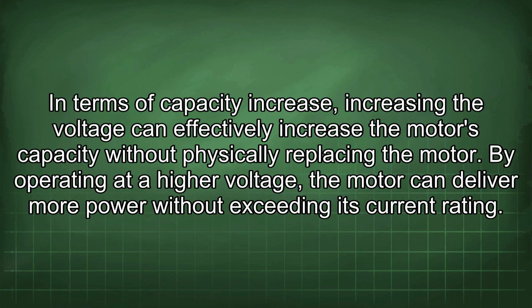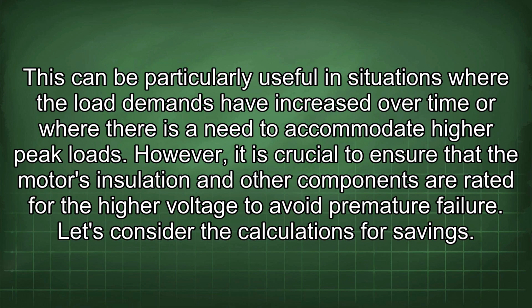In terms of capacity increase, increasing the voltage can effectively increase the motor's capacity without physically replacing the motor. By operating at a higher voltage, the motor can deliver more power without exceeding its current rating. This can be particularly useful in situations where the load demands have increased over time or where there is a need to accommodate higher peak loads. However, it is crucial to ensure that the motor's insulation and other components are rated for the higher voltage to avoid premature failure.